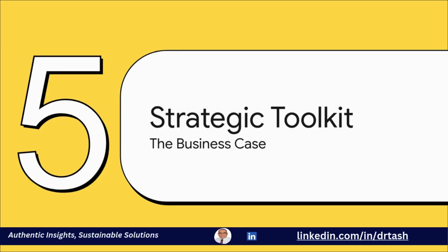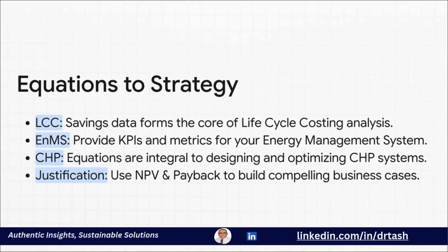Okay, last section. Let's zoom out a bit. We need to connect all these nitty-gritty calculations to the high-level strategy you're using to run your energy programs. This is where the rubber meets the road, where your numbers turn into a rock-solid business case. Think about it. Every single equation we've talked about plugs directly into these bigger picture concepts. That savings number you calculated for a blowdown heat recovery project becomes the cornerstone of your life cycle cost analysis. That steam leak mass flow you got from Napier's formula, that's the hard data you use to calculate the net present value and get that repair project greenlit.